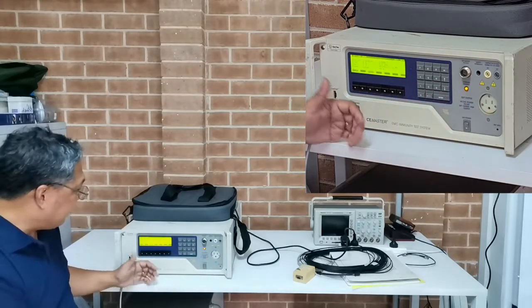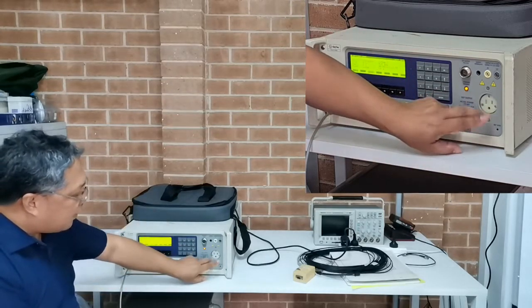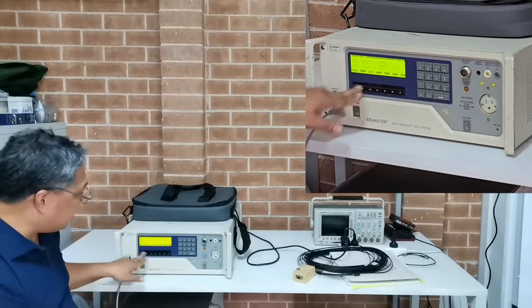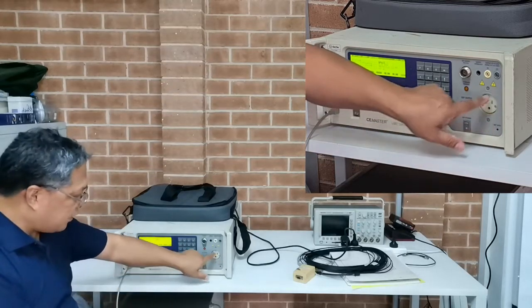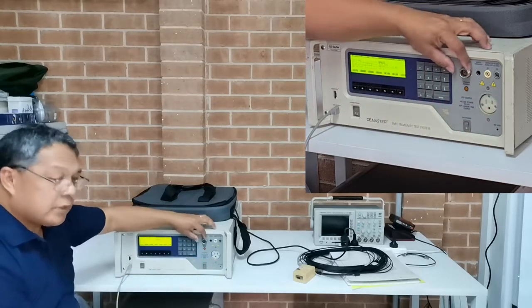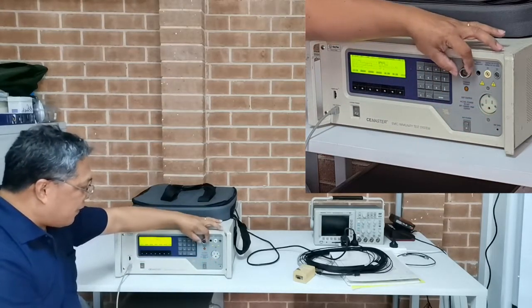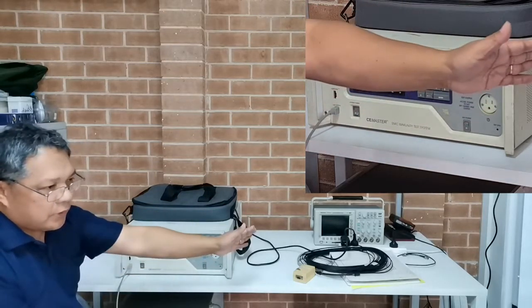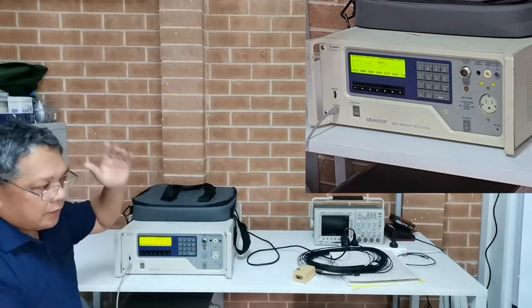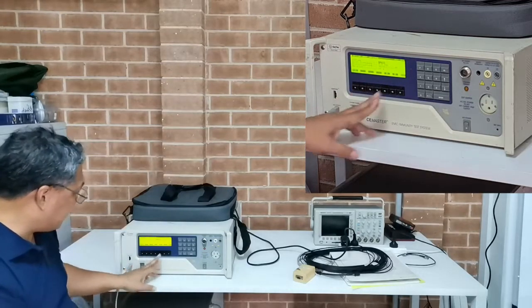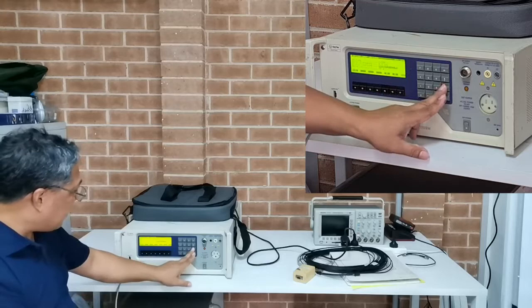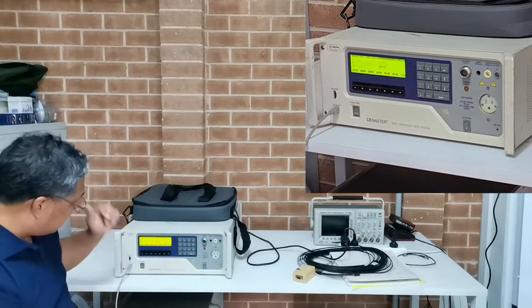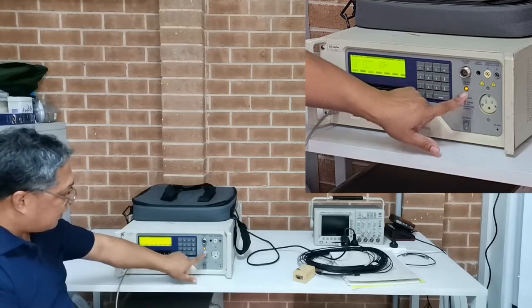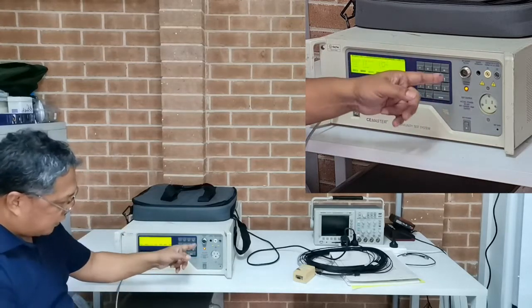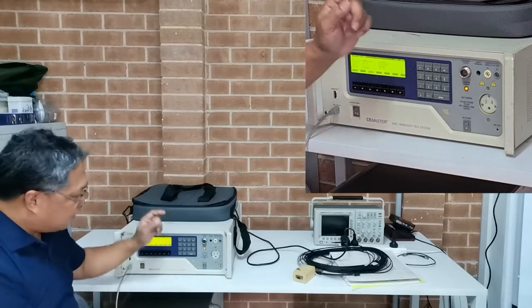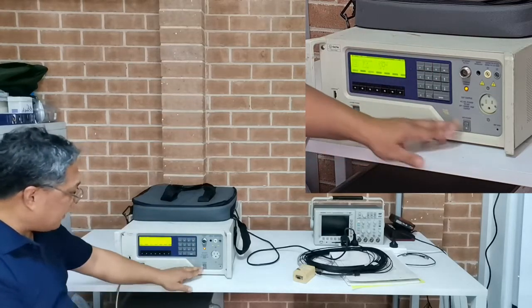But because I can't apply the EFT through the EUT supply, I have to use the clamp. The burst is coming out through the clamp, and this clamp goes through the decoupling network, so I apply it directly through all the lines together. In here I can choose the clamp, which is one, and then the voltage present, and the high voltage will be present on the EFT output on the clamp, because it's running now.